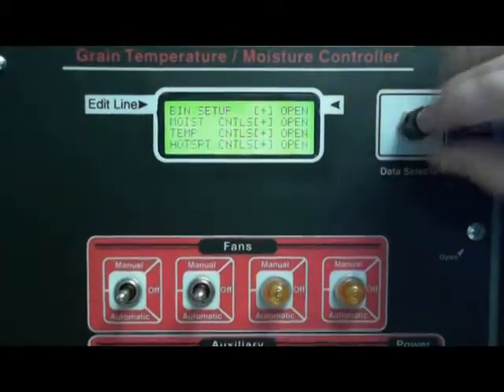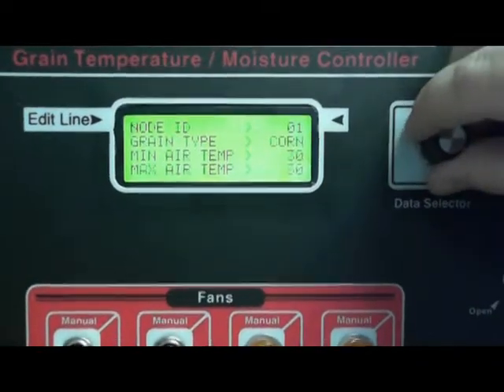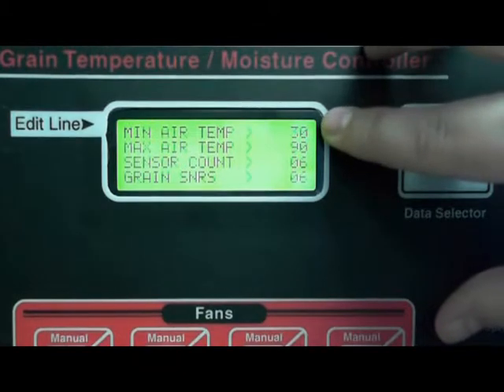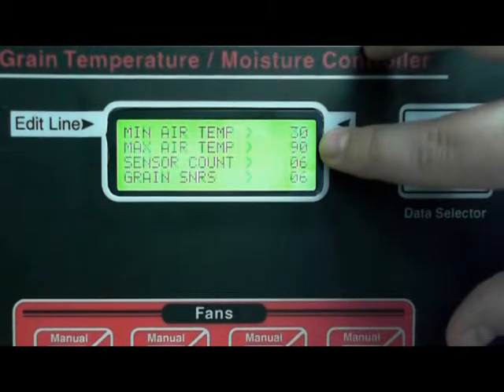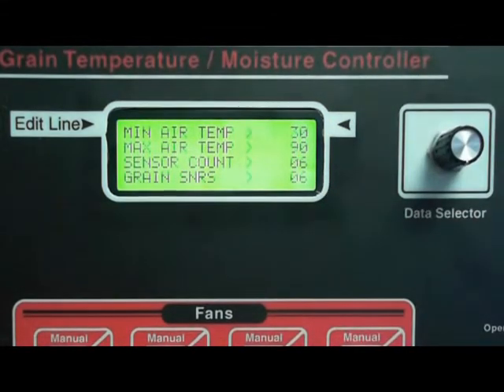Let's open bin setup here. We want to make sure that your minimum air temperature is set to 30 degrees and your maximum air temperature is set to 90 degrees.